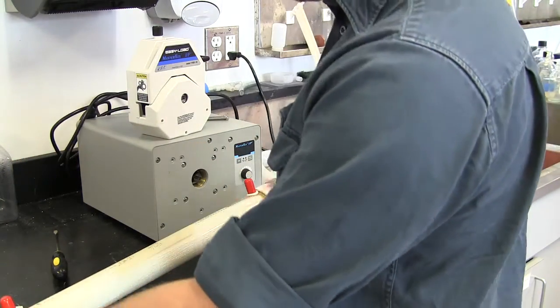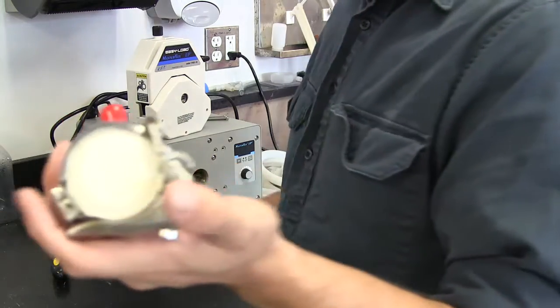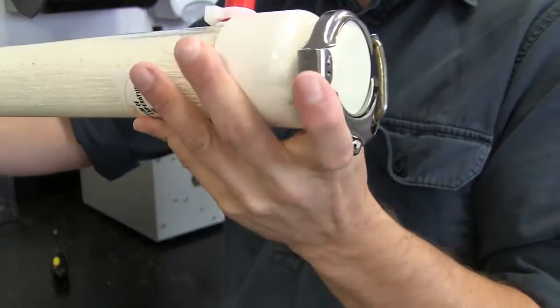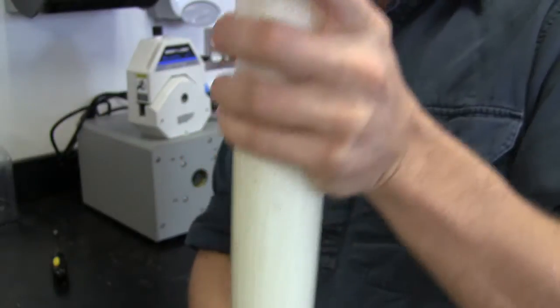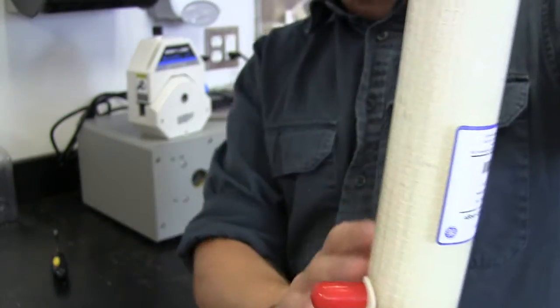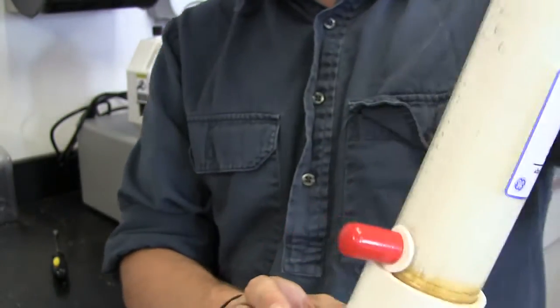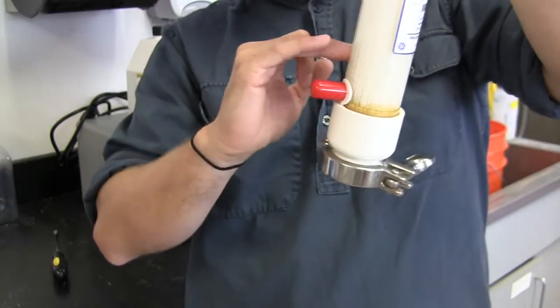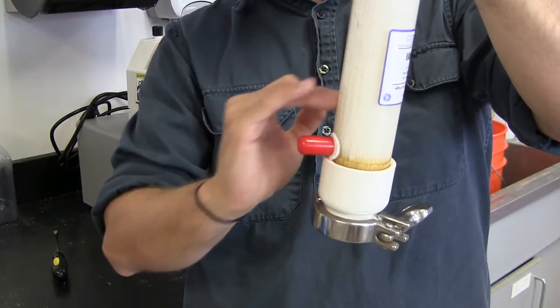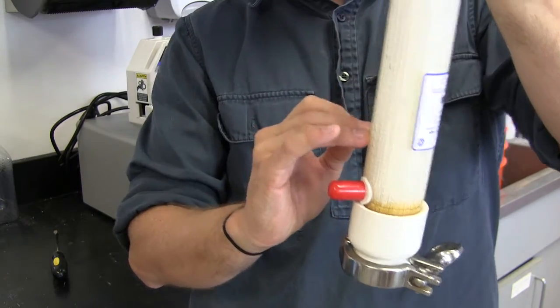Okay, so that's the TFF. You'll note that it's sealed at both ends so that water cannot leak out, and a good TFF is one that remains wet. If you see it dry, it's probably not in very good shape. At least when you hold it up, you should see liquid pool up to about this level here. Without that, your TFF's not looking very good.